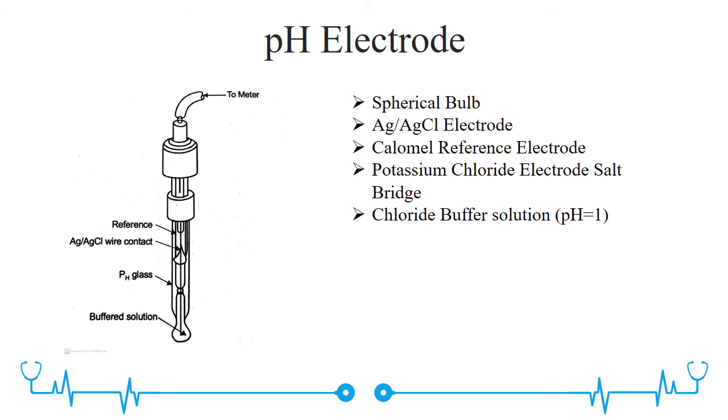Inside the glass bulb, a silver-silver chloride non-polarizable electrode is immersed in a chloride buffer solution of pH 1. The other side of the glass bulb is exposed to the solution of unknown pH. The connection to the potential measuring circuit is through a potassium chloride salt bridge and calomel reference electrode. Today, the glass electrode and reference electrode are available in the same enclosure.